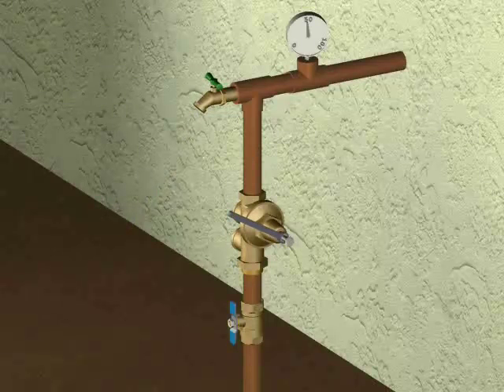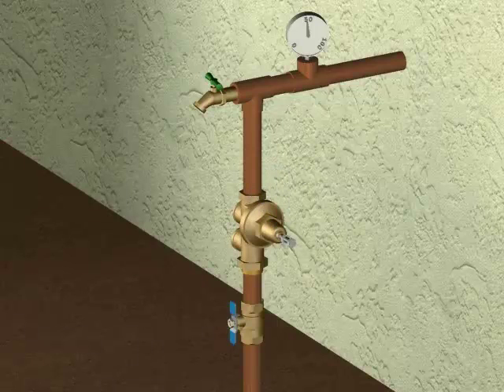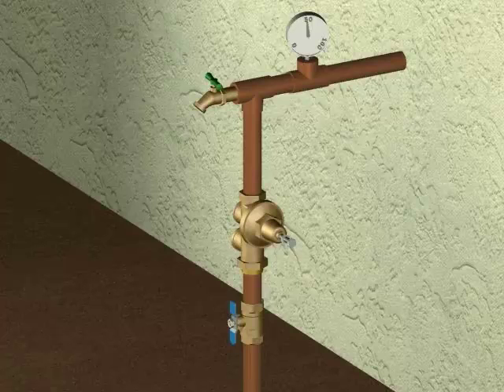Tighten the lock nut when your desired pressure is set. Observe your gauge for a few minutes to make sure pressure is constant, showing cartridges are seated properly, and that there are no internal leaks within the valve.